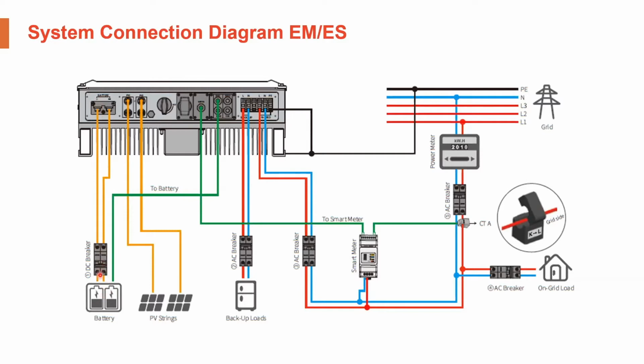We do recommend, if the battery that you're using does not have an internal DC isolator or a DC breaker, then we do suggest that you install an external DC breaker. But there are regions around the world that, regardless of whether the battery does have an internal breaker, stipulate that you install an external DC breaker. So I would read your NEN rules to see what is a must or must not have in terms of the DC connection.